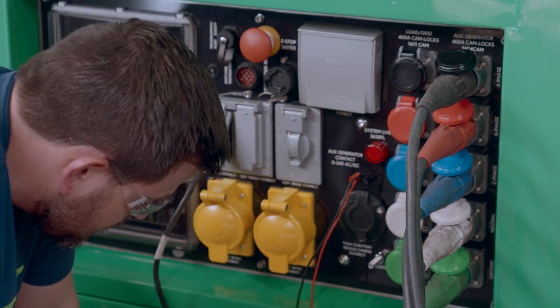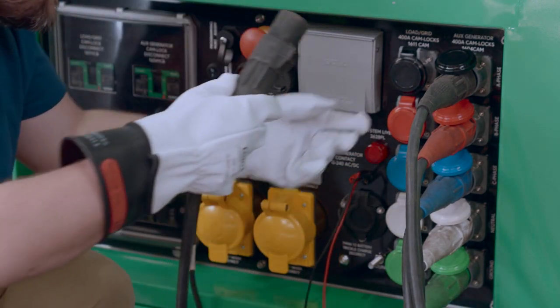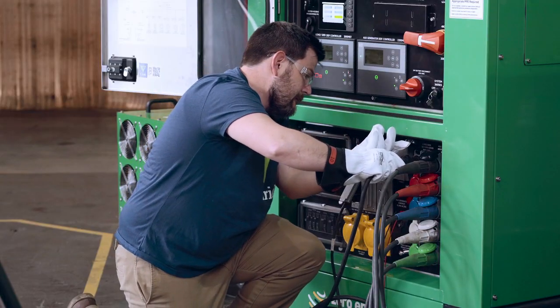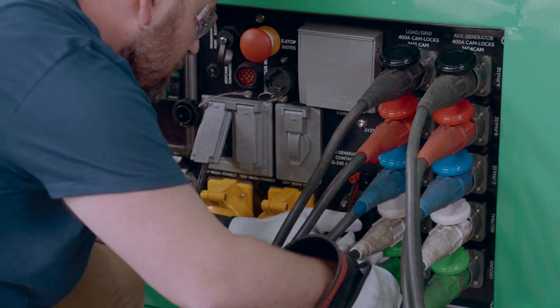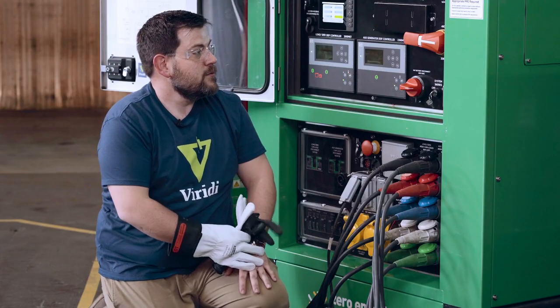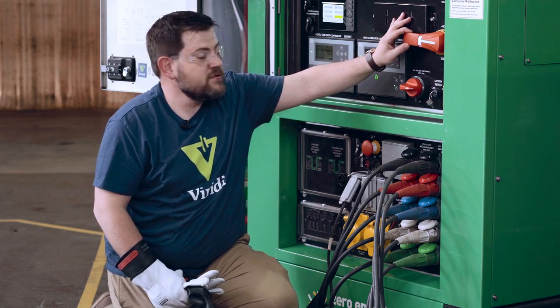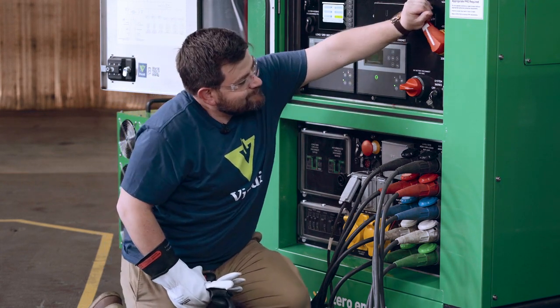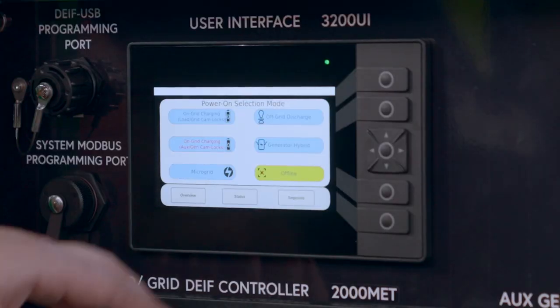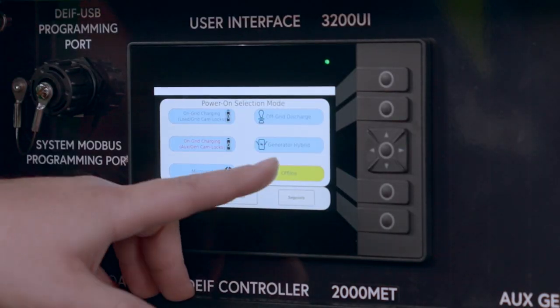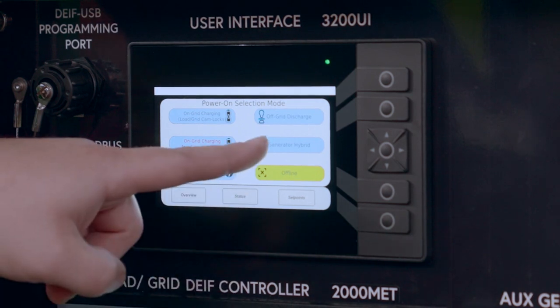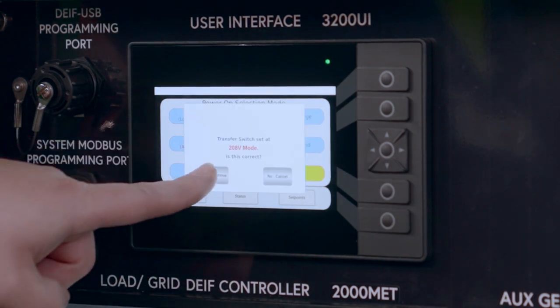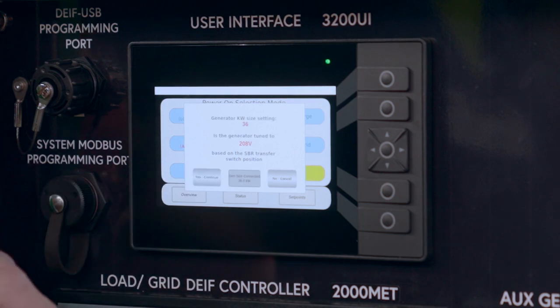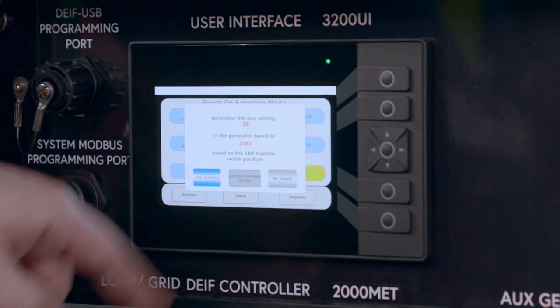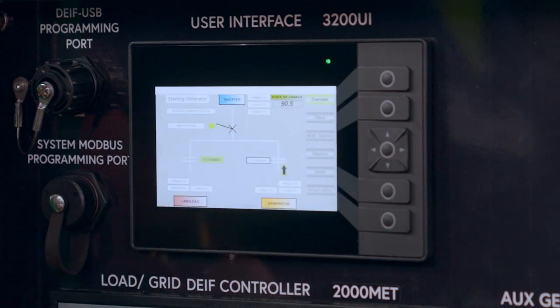I will then connect our load to our load grid cam locks. Again, we will be running this mode at 208 volts, so I will put the transfer to the 208 volt position. And then from the user interface, select our generator hybrid mode. Follow the on-screen prompts for 208 volt mode. Load is set up for 208 volts. And then at this point, you can select your generator size you are paralleling with. Ours is the 36 kW generator, and that is set for 208 volts as well.